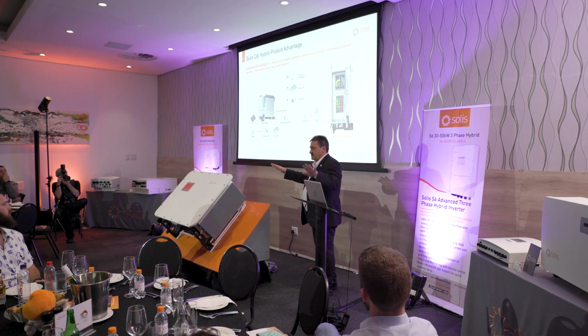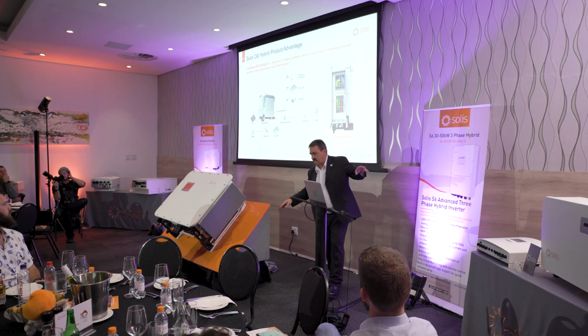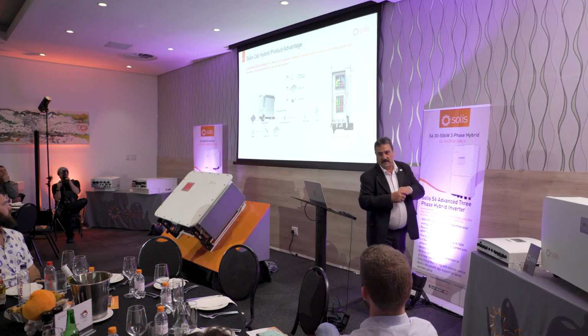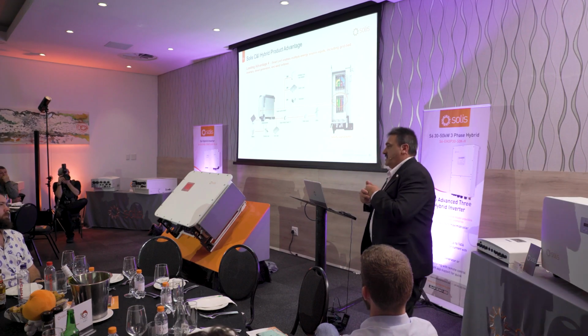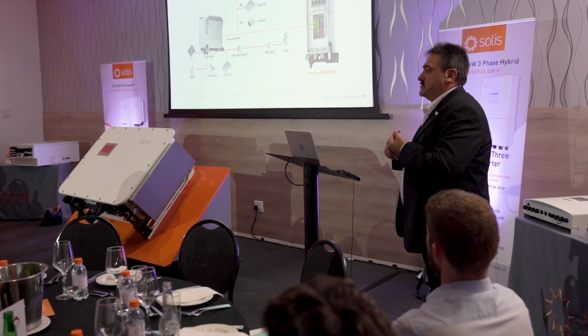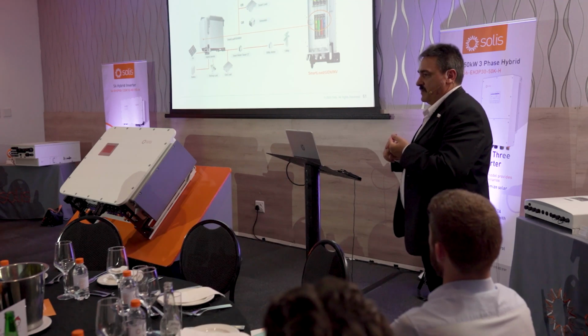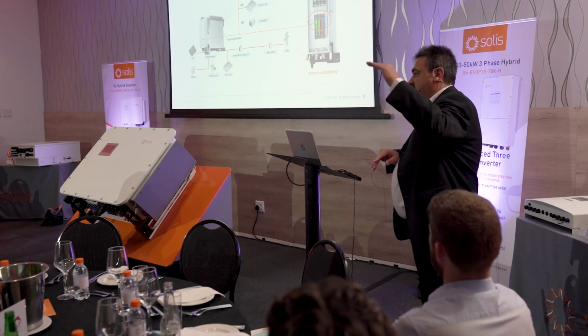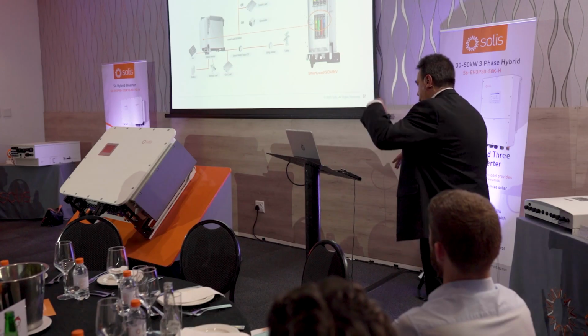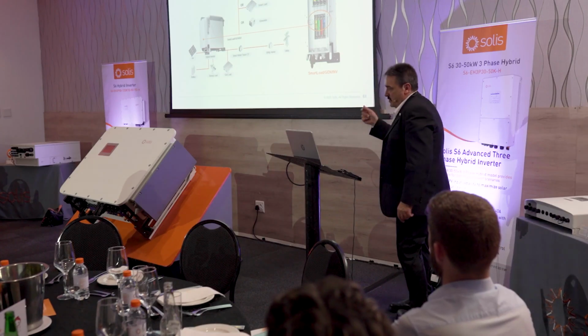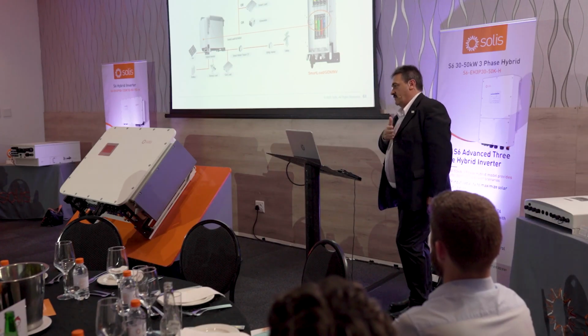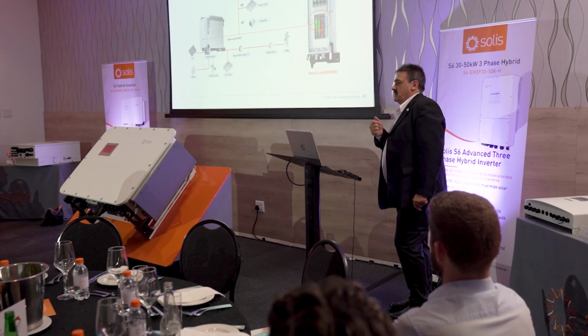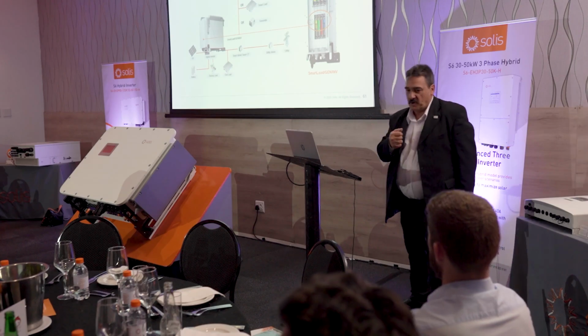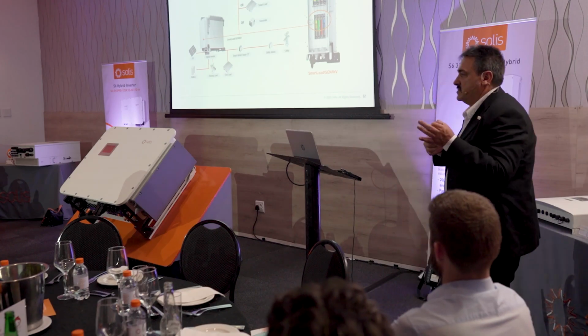Everybody has done C&I systems, even grid tie ones. One of the biggest things we have to deal with every day is over voltage alarms on the PV systems, right? Because the voltage of the system just creeps up. It's 253, and the inverter says, listen, you're on alarm 1, you've got 40 seconds to correct yourself, or otherwise I must disconnect. Right? The biggest problem with that is the size of the cable.